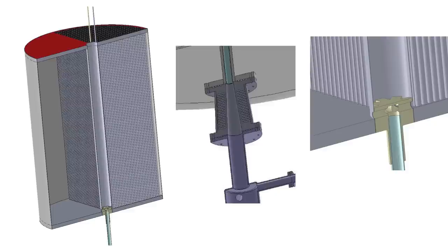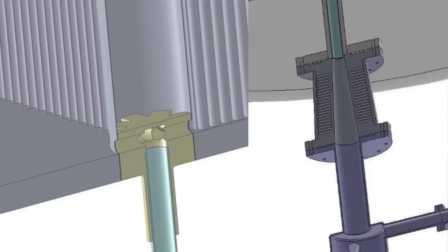Lots and lots of pipes. There are about 3,700 pipes in this thing, which is a lot. I'm going to try to thin that number down. And there is the freeze plug. When the power goes off to the freeze plug, it's a quick melt and it drops down. So we have an additional measure of safety. Even if the scram switch doesn't work for some reason or another, soon that hot salt will melt out and down it goes into the dump tank.